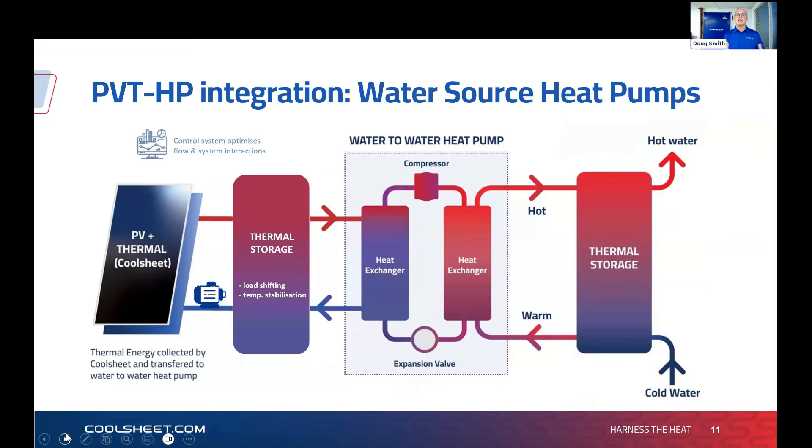Unless you're cycling swimming pool water directly through the Coolsheet — which it's rated to handle, including salt water or chlorinated water — you generally get a more effective, faster ROI by pairing with a water source or hybrid heat pump. It's a virtuous loop: you take the cold side of the heat pump and run that through the back of the solar panels, getting a very nice delta T and harnessing a lot of thermal energy, effectively working as a pre-heat to lift the inlet temperature to the heat pump.